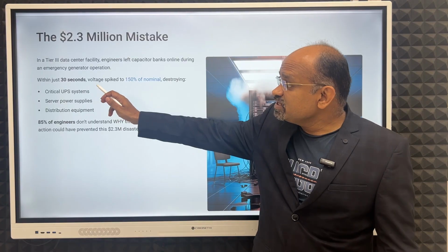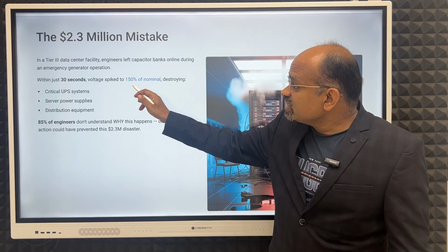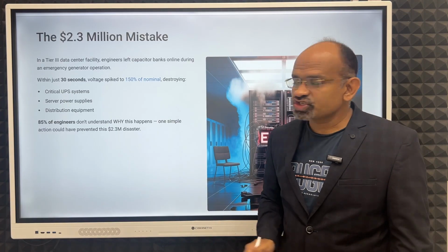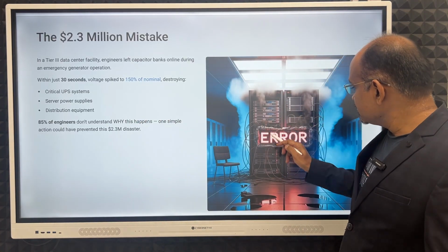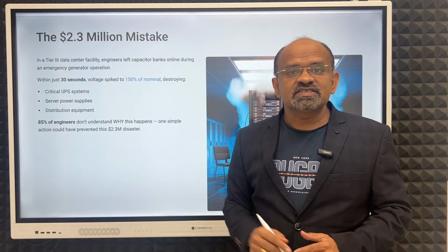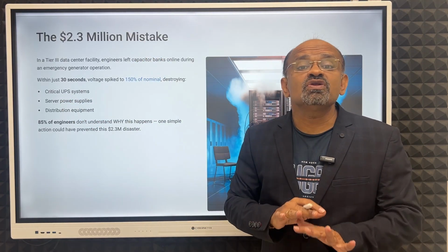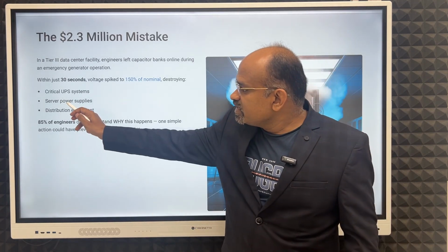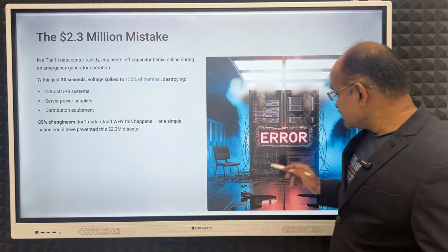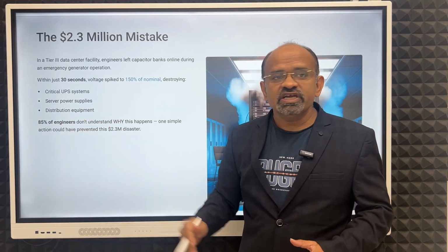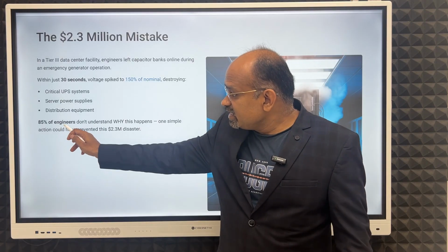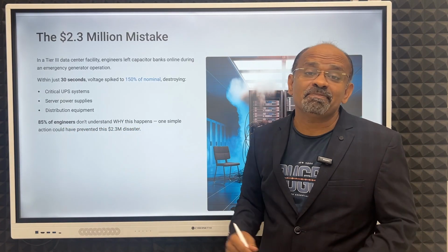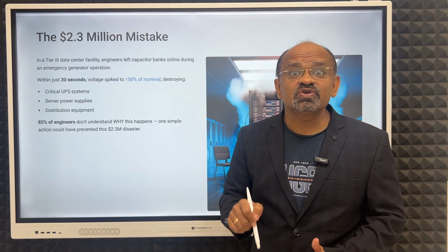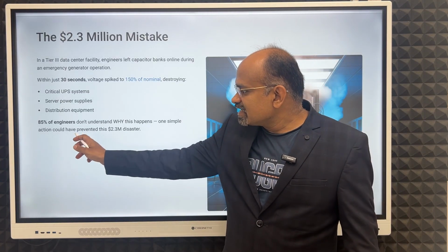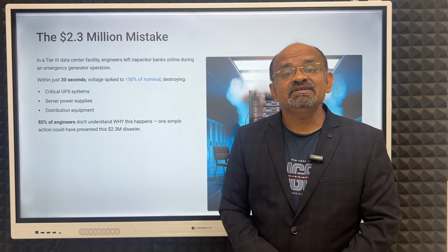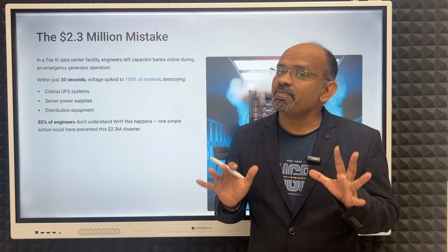Then what happened? Within just 30 seconds, voltage spiked to 150% of nominal voltage, destroying things. What was destroyed? The critical UPS system. At a high voltage such as 150%, it will not survive. Then the server power supplies in the servers were gone, and the distribution equipment too. 85% of engineers don't understand why this happens, and we are going to see why. One simple action, switching off the capacitor bank, would have prevented this $2.3 million disaster.